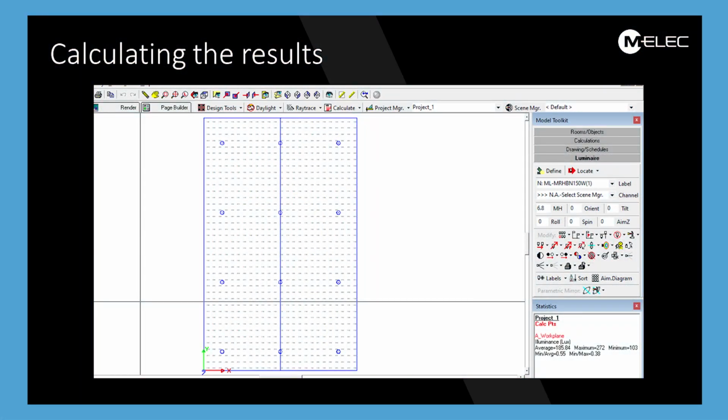Okay. So this is what we've got, and is this your calculation page, or is this still the grid that... No, this is the calculation plane now. So I run the calculation based on how I put them in. It's telling me I've got 185 lux at 0.55. So to me, that's compliance to Australian standard, because your 0.5 is your required uniformity for basic rooms. And as you saw, it had to be 160 lux. So yes. It's now telling me that I've got the spacings correct, because in the estimator they were incorrect. Spacings are correct. I've got the right lux levels. I've got the right uniformity.